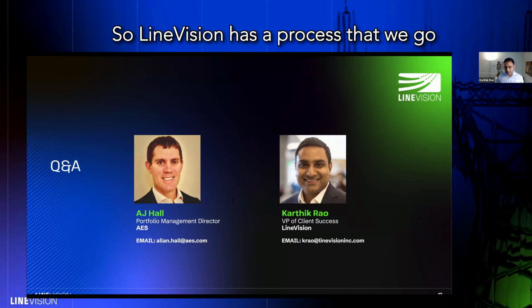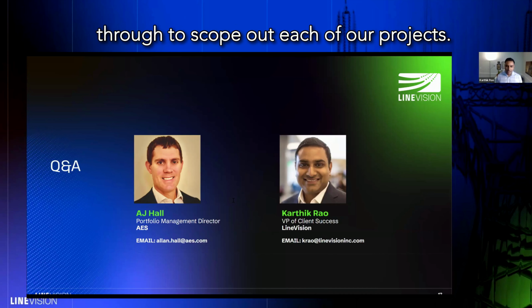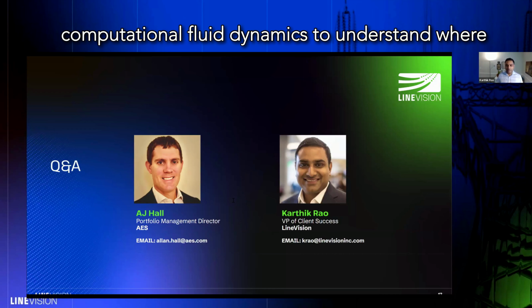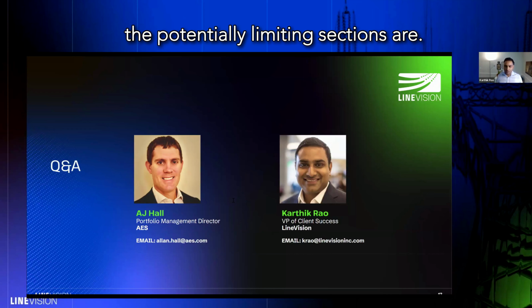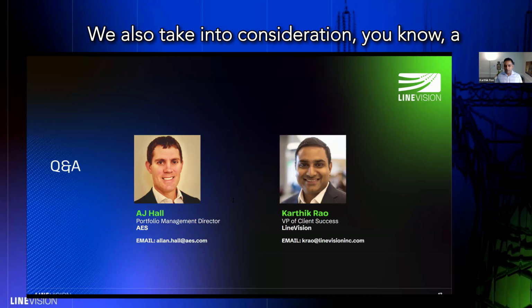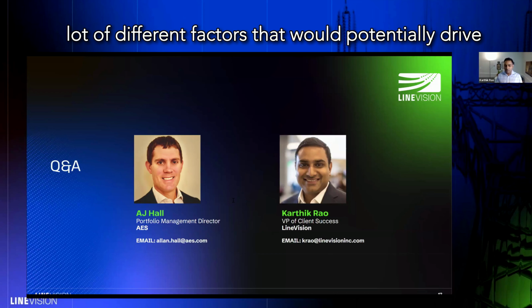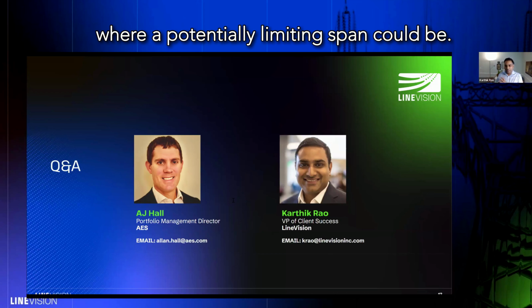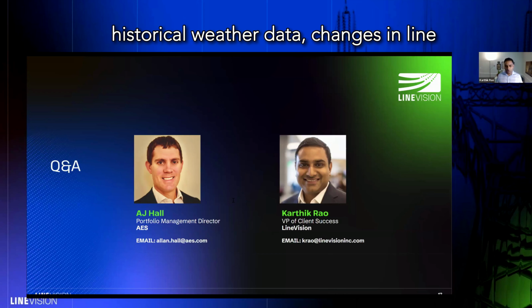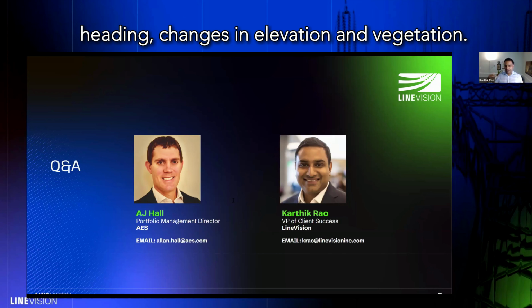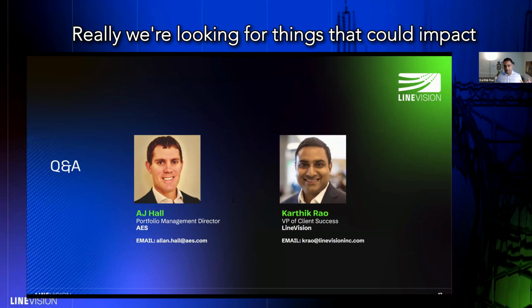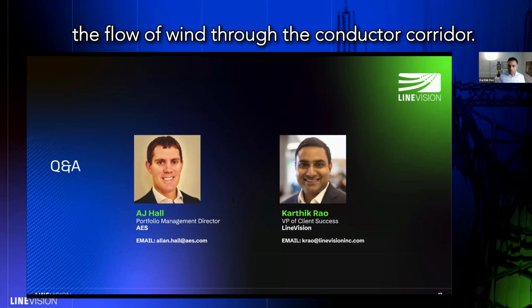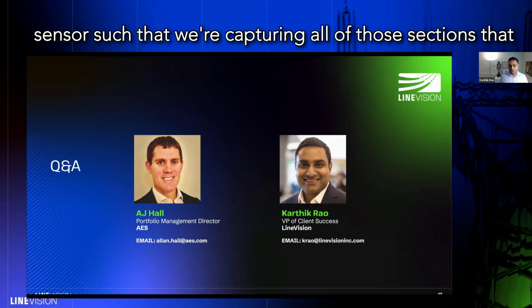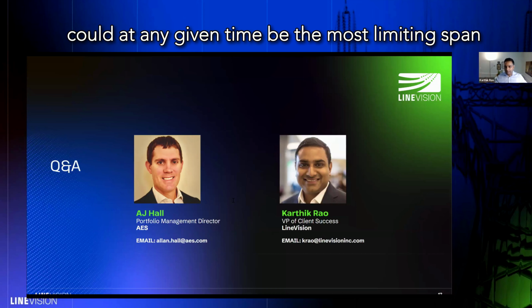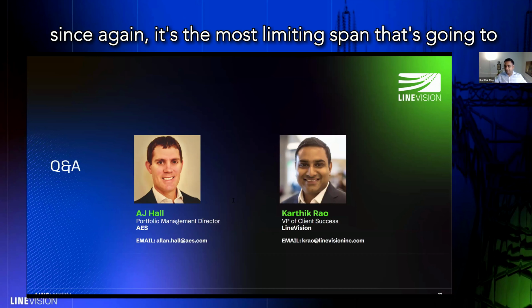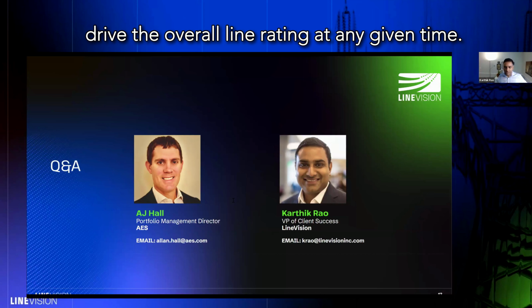LineVision has a process we go through to scope out each project. It's a combination of running computational fluid dynamics to understand where the potentially limiting sections are, and considering factors like historical weather data, changes in line heading, elevation and vegetation. We're looking for things that could impact the flow of wind through the conductor corridor, and we want to place sensors to capture the most limiting span, since that drives the overall line rating at any given time.